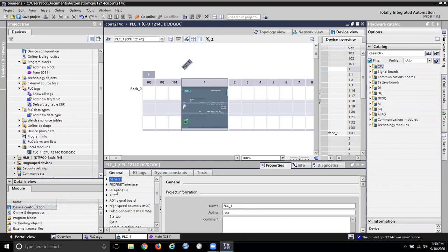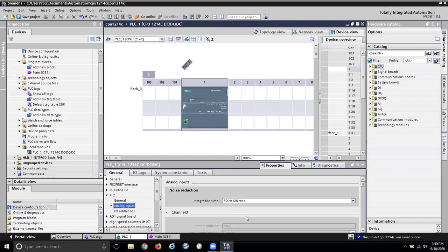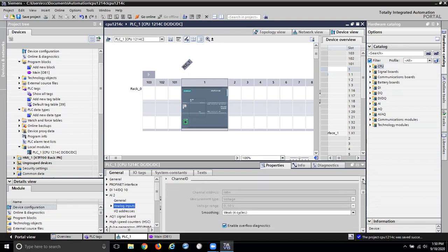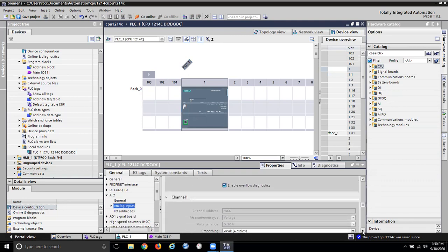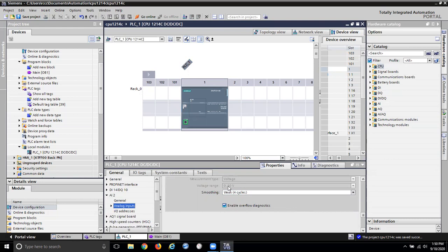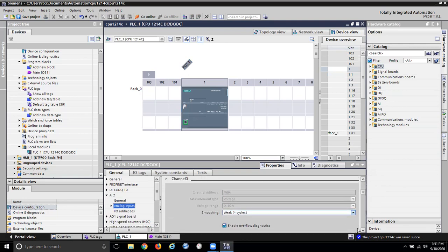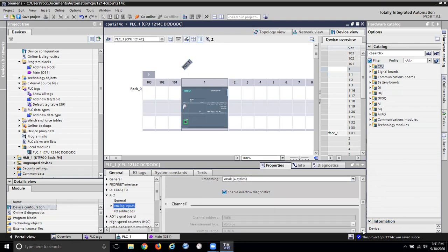I've got 14 digital inputs and 10 digital outputs. I've got my analog inputs, and I've got channel 0. The channel address is IW 64 and it's set up to be 0 to 10 volts. This does not look configurable — I think it comes set up that way and there's nothing you can do about it. So I've got channel 0 and channel 1, which are both set up to read 0 to 10 volts. My channel addresses are IW 64 and IW 66.